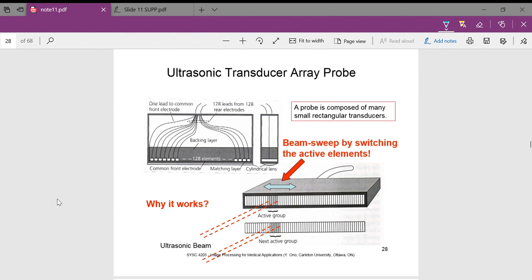Here you can see our transducer from one direction, and if we twist it on its side, from the other direction. Each of these elements is a different transducer — in this particular one, there are 128 different elements. Each is set up with a backing layer and a matching layer in front, with electrodes on either end, because these are piezoelectric crystals. There is also a cylindrical lens that can help steer the beams. This can be done mechanically or electronically.